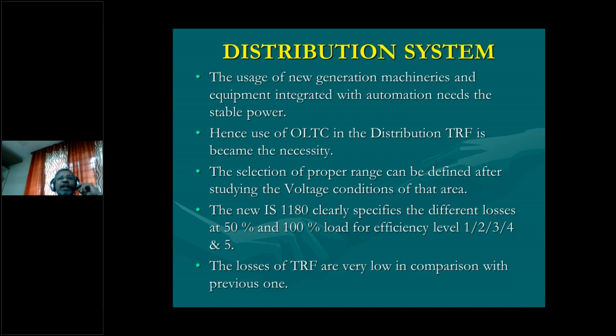Fortunately, in this new IS standard, they have clearly specified the 50% and 100% load losses. So whenever you go for testing, you take the loss. Previously, we used to consider no load loss and load loss. Now they only talk about 50% and 100%. And let me tell you honestly, the losses of this new range of transformers are very low compared to the previous ones.